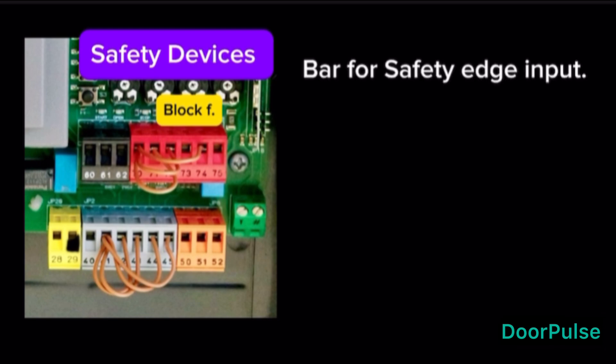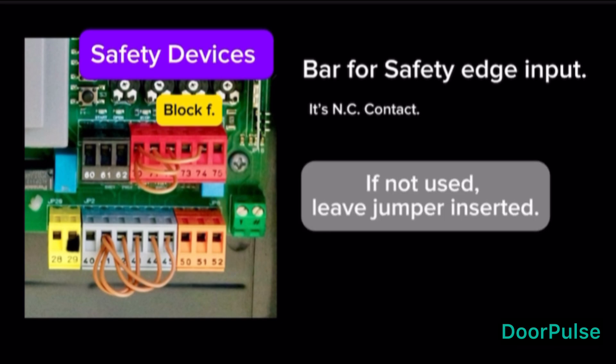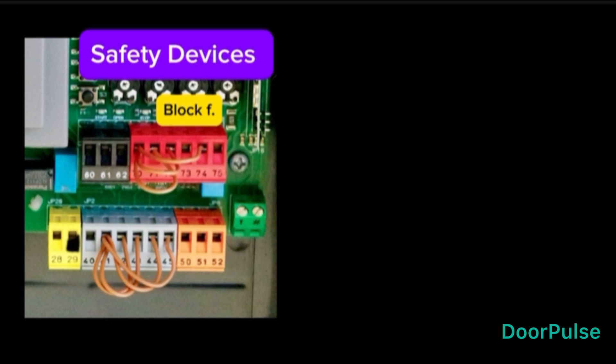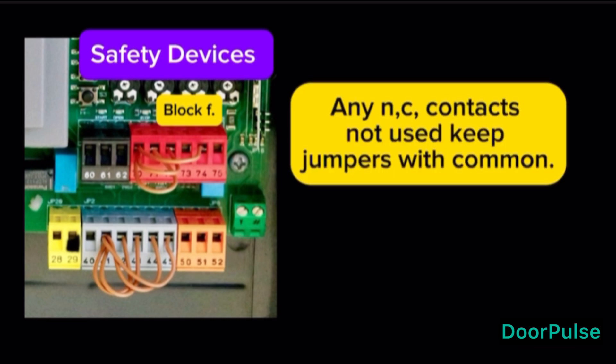Terminal 74, bar for safety edge input. It's NC contact. If not used, leave jumper inserted. NC contacts not used, keep jumpers with common.